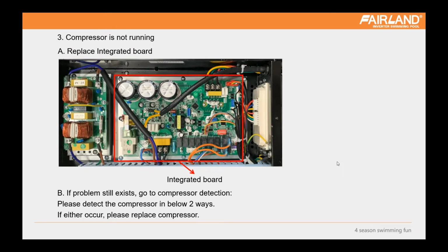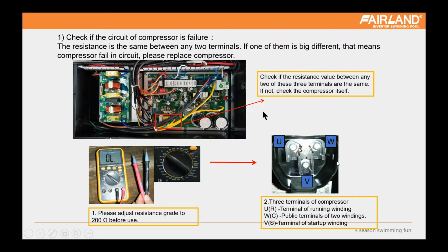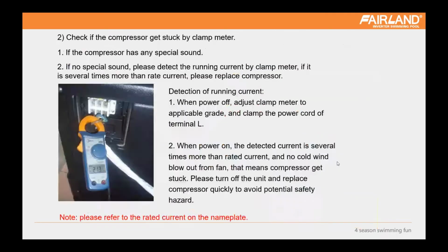And if the problem is that the compressor is not running, then also check the compressor system, including the wire on the integrated board. Then replace the integrated board. Then check the compressor for short circuits and resistance, and also check the start current, to check if it gets stuck or not.